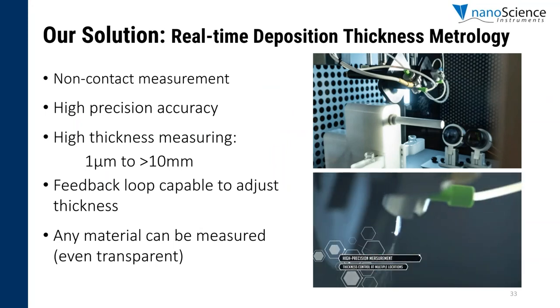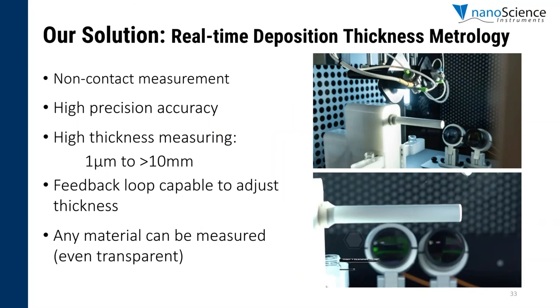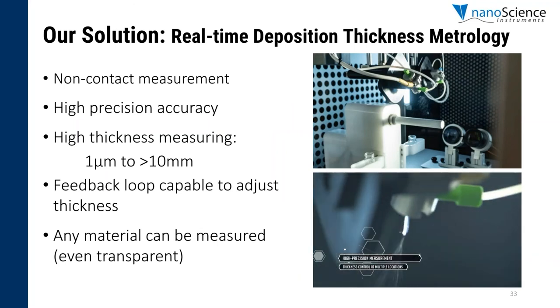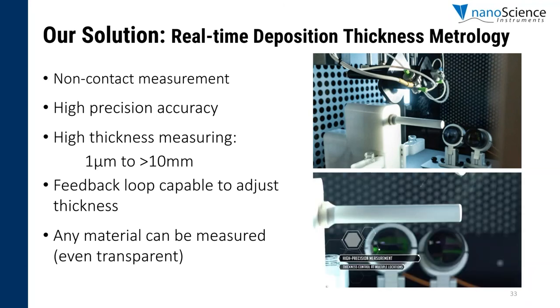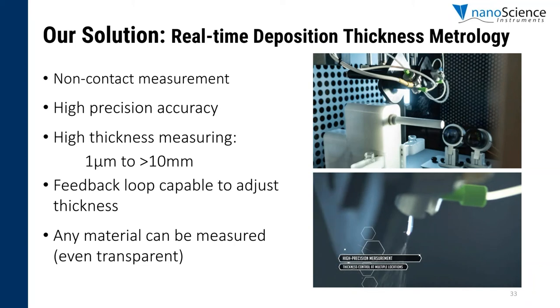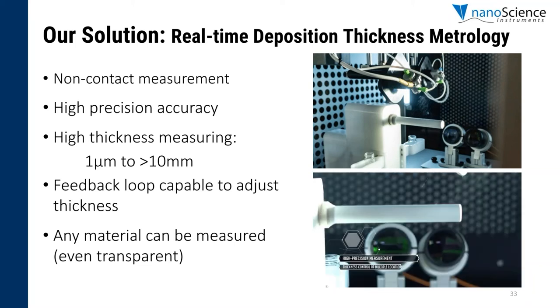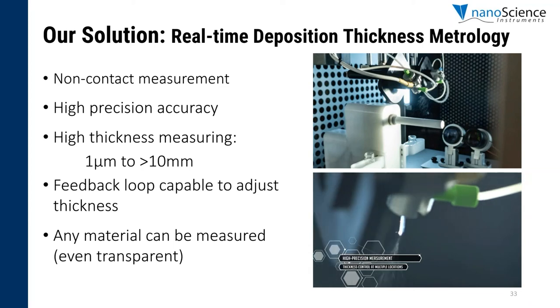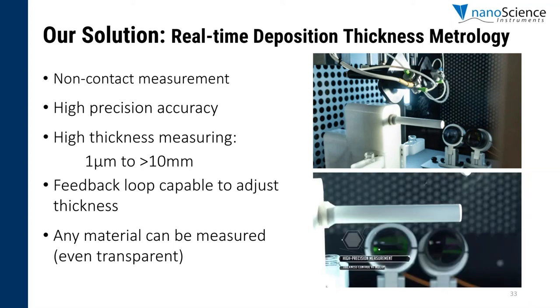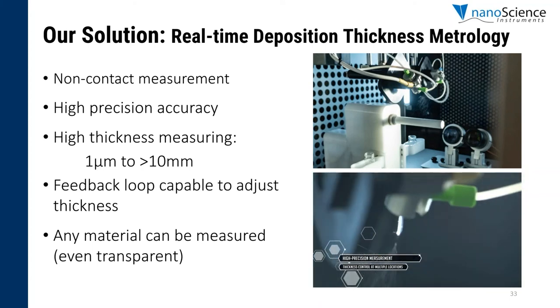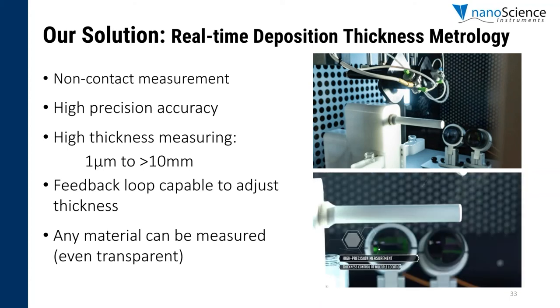Our solution is real-time sample thickness measurement. We work directly with our customers to engineer this accessory to their application needs. It is always a high precision accuracy package that can measure over 10 millimeters in range. An advantage of our metrology system is that it's a non-contact measurement, allowing the sample to reach a desired thickness without damaging the sample or its desired properties. A feedback loop can also be implemented with the emitter motion to properly reach the thickness.